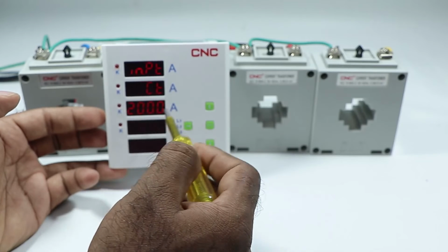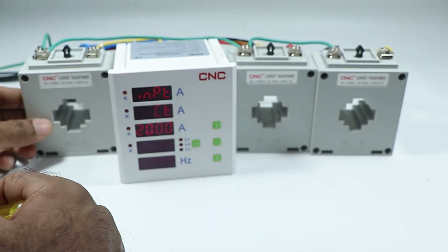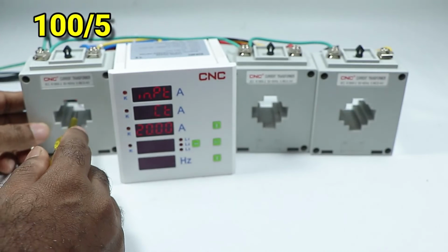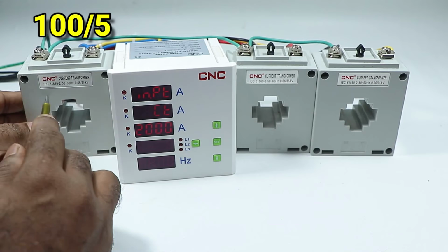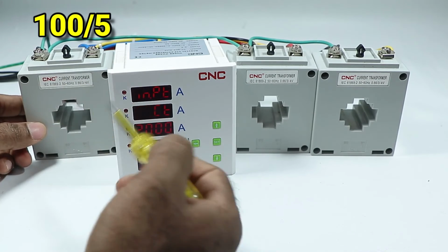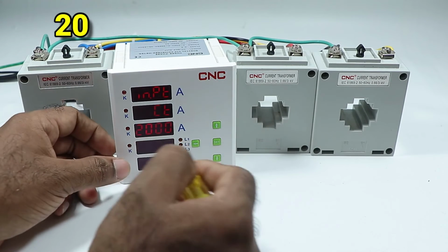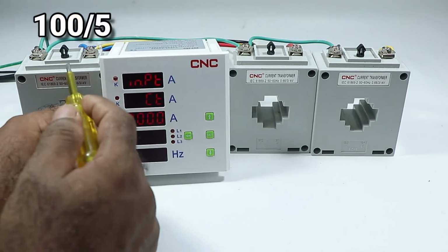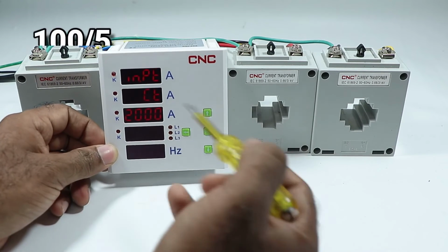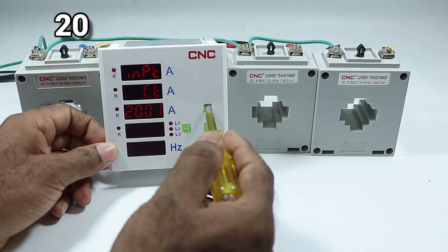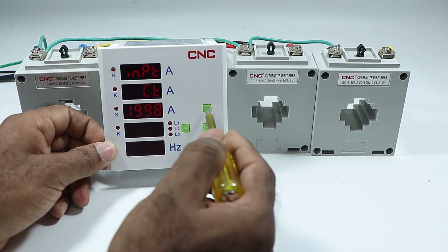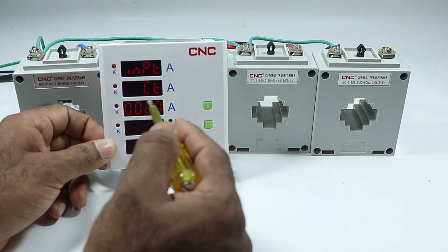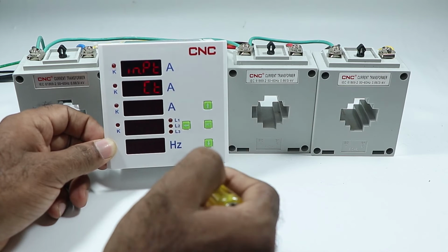For setting the ratio of CT, you have to do one thing. The CT I have now has a ratio of 100 by 5. Divide 100 by 5, and the answer you get, you set here. 100 divided by 5 equals 20, so I have to set 20 here. Let's set this as 20, and once selected, press the button.